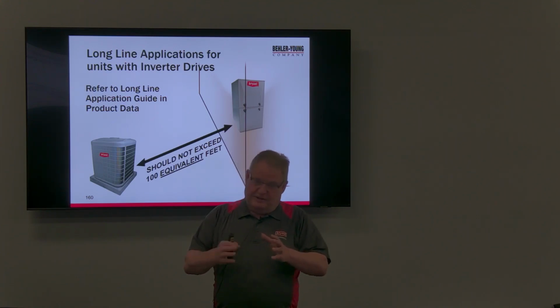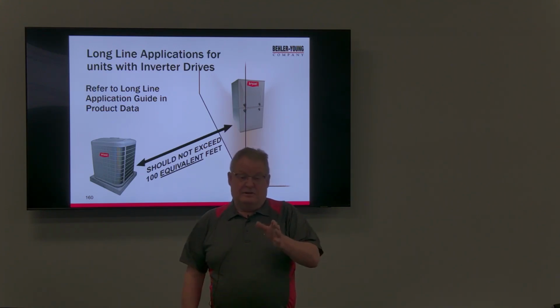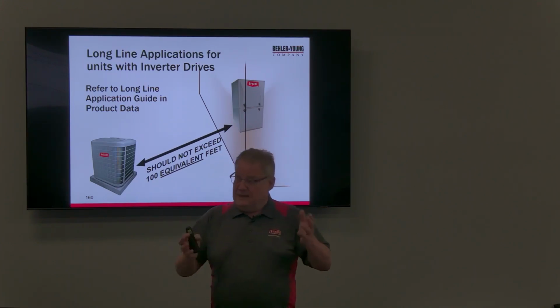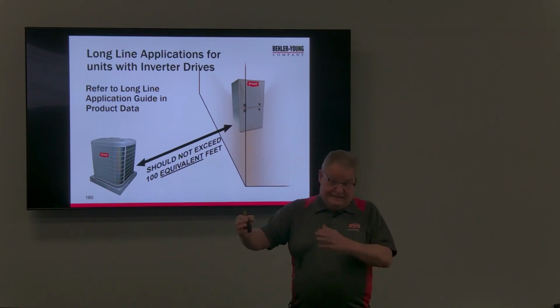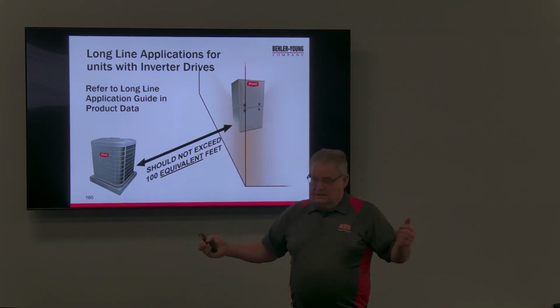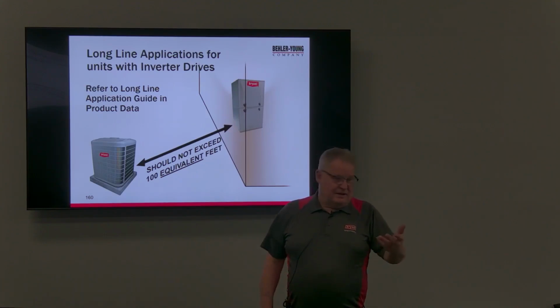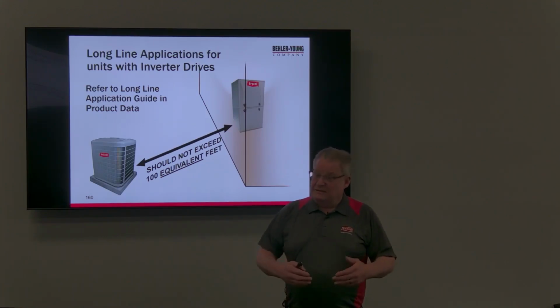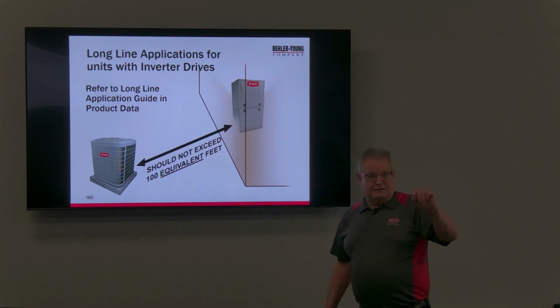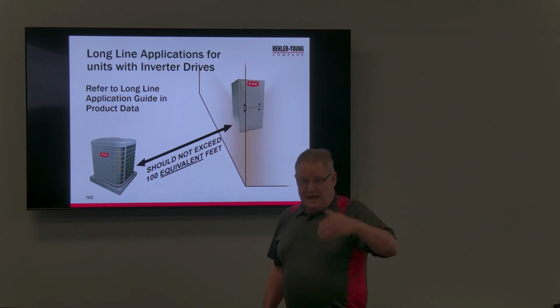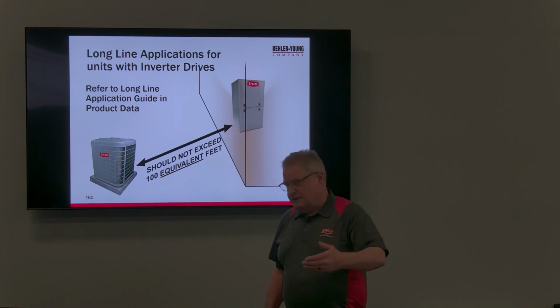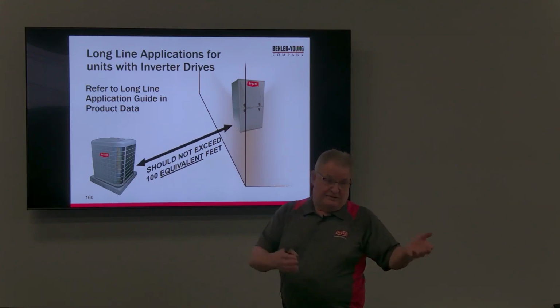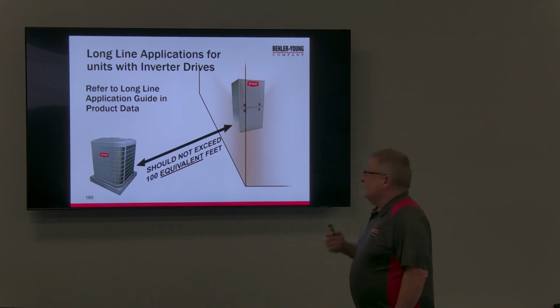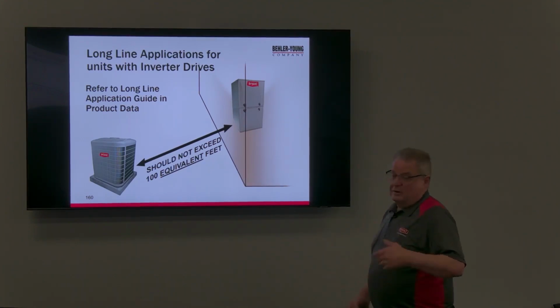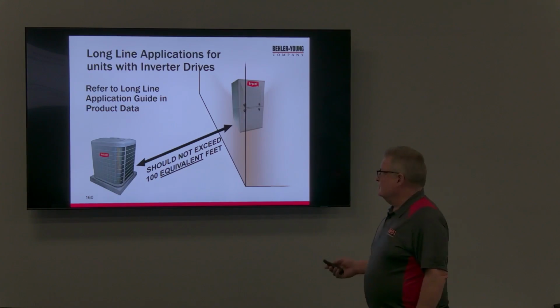You'll get used to it, but when you first get it, it'll tell you factory charge, required charge. So it might tell you right off the bat you need to add this much. Well, what happens is you install it, you've got a 15-foot line set, and you figure your charge should be good. Well, it's not. So the newer units, the 454B units, you want to check that because a lot of them can no longer hold enough charge for 15 feet. So if you start out thinking it was low from the factory, it was actually that the system just can't hold it all from the factory.